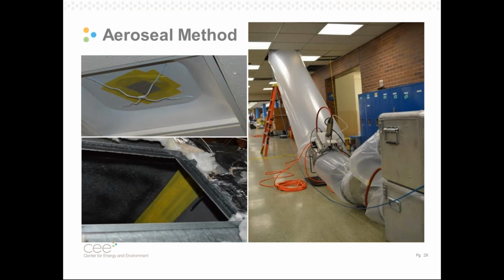Oh, jumping ahead. This is what an Aeroseal system looks like deployed. I mentioned we seal upstream and downstream. On the top left, we're sealing the final diffusers. On the bottom left, we're sealing at the reheat coil on a VAV box. And then on the right, we have our Aeroseal system hooked up to an access panel, and it is about ready to deliver sealant and flow and seal that ductwork.